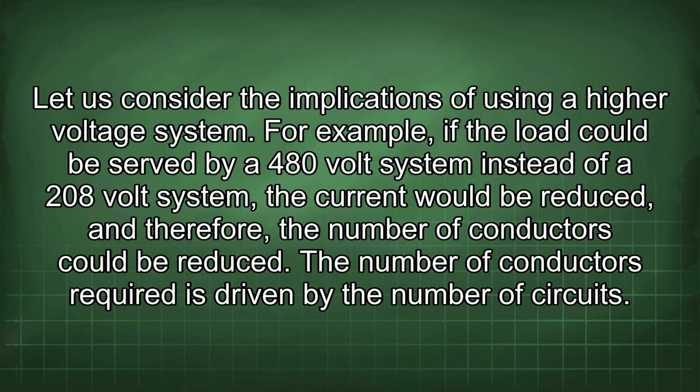Let us consider the implications of using a higher voltage system. For example, if the load could be served by a 480-volt system instead of a 208-volt system, the current would be reduced, and therefore, the number of conductors could be reduced.